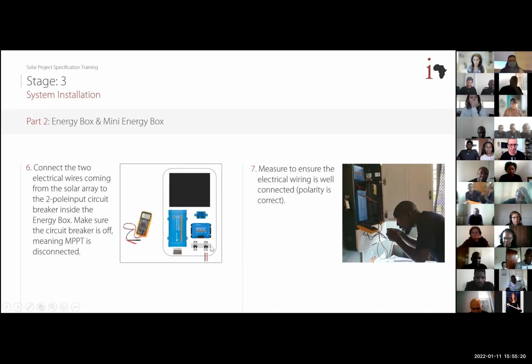Once you connect the solar array to the terminals, also verify that the circuit breaker is disconnected so power does not continue to the charge controller prior to that. Then measure the voltage level at the terminals to see they are connected correctly, polarity wise. This also lets you confirm the panels are connected accurately and all connections are right - if it's a mixed connection, you know what voltage to expect.